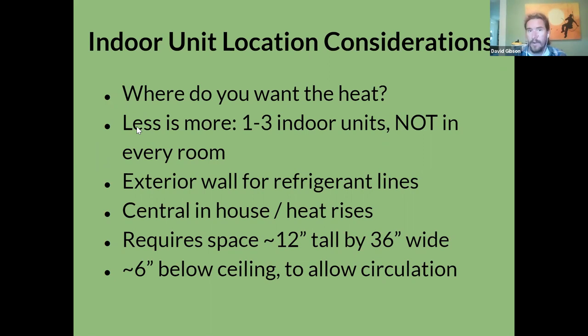And so they generally require a space, depending on the exact type of indoor unit. The typical ones require about 12 inches of height and 3 feet of width to mount them on the wall. And then they need to be about 6 inches below the ceiling. Most of the units will pull air from the room in from above and then blow it out below. And depending on the manufacturer, they can be a little bit closer to the ceiling. Different manufacturers have slightly different size units. But this is kind of a typical one.